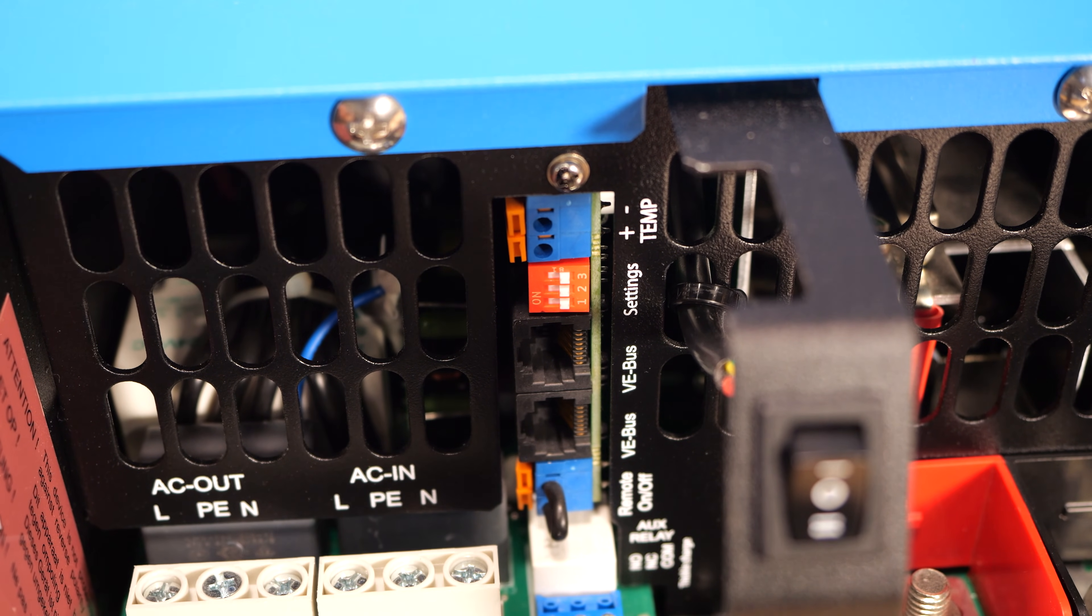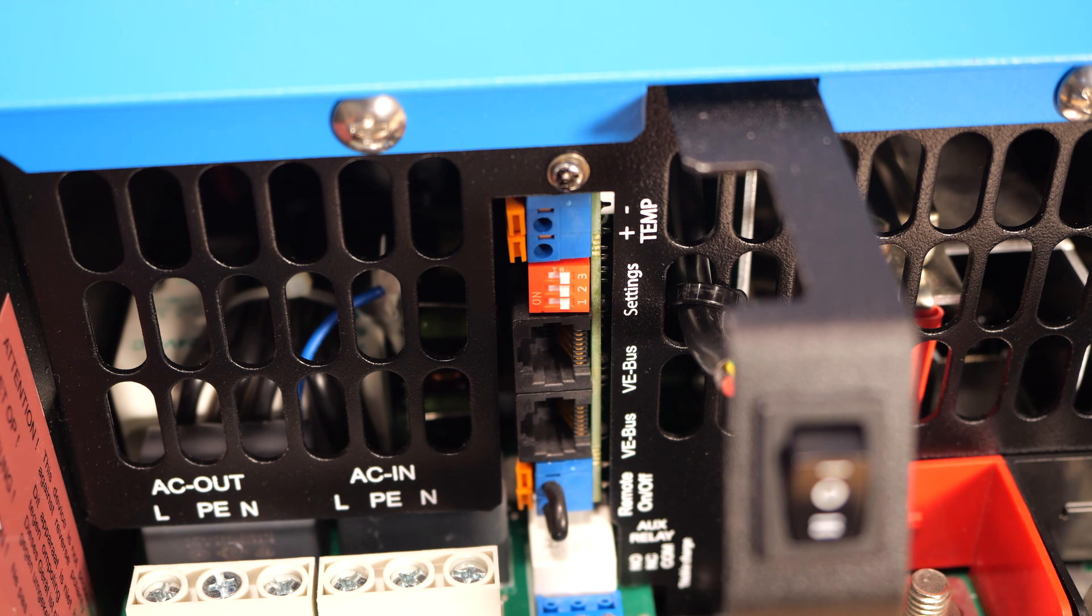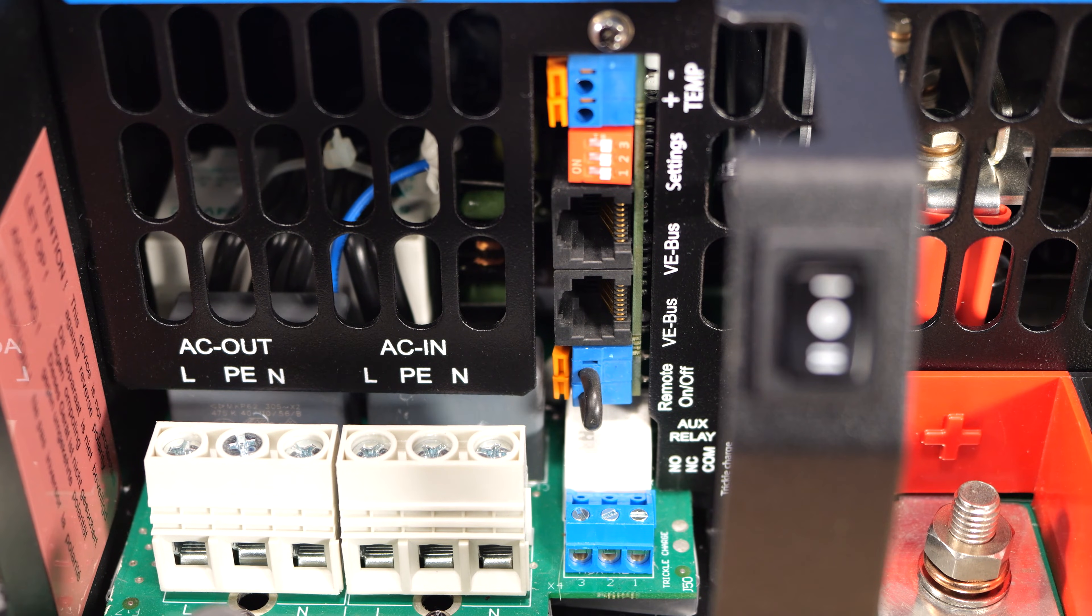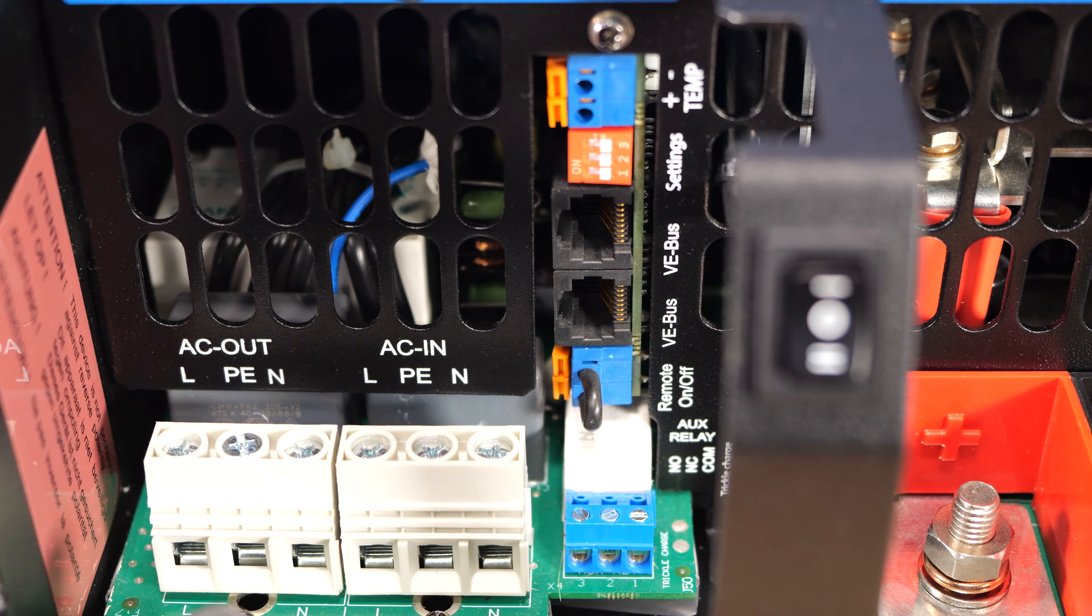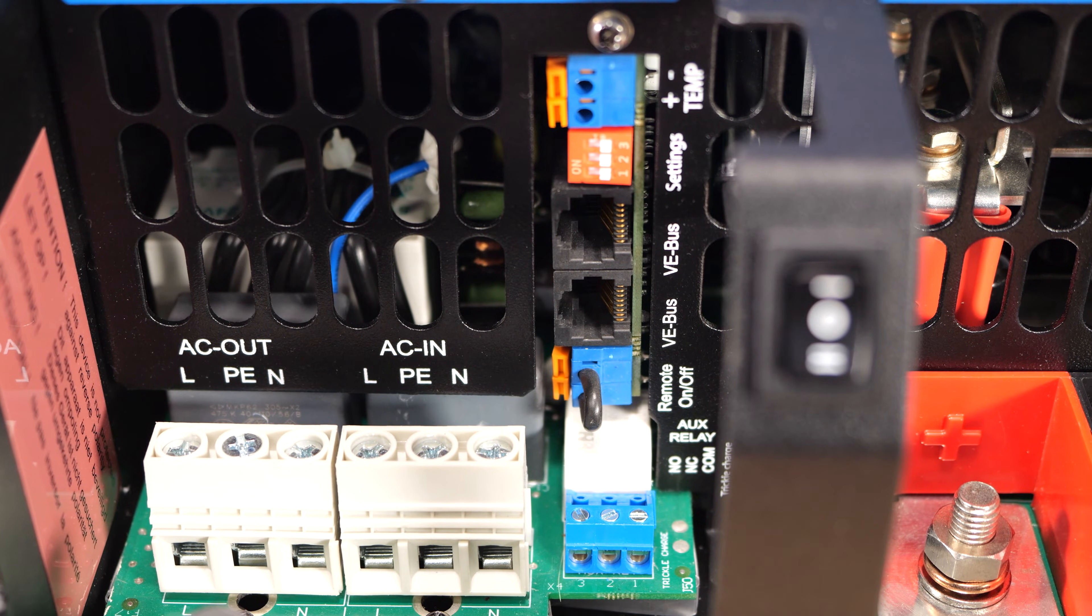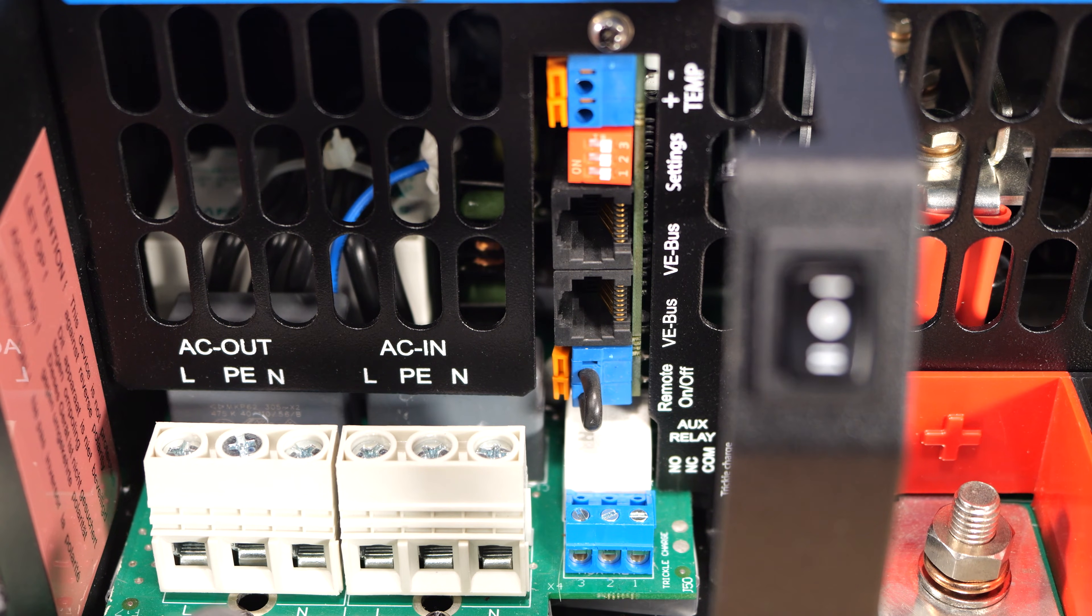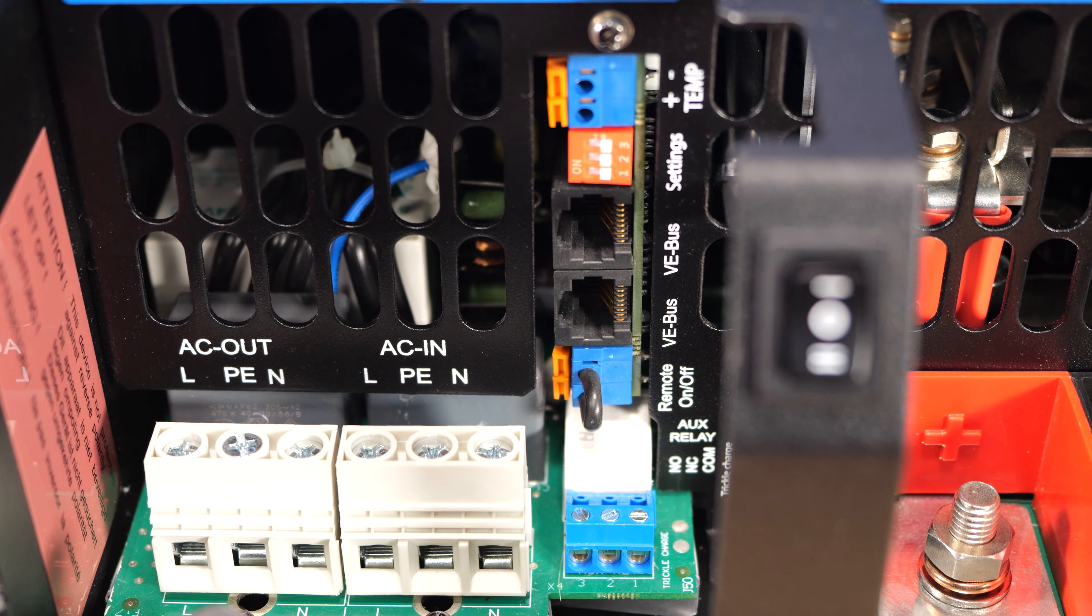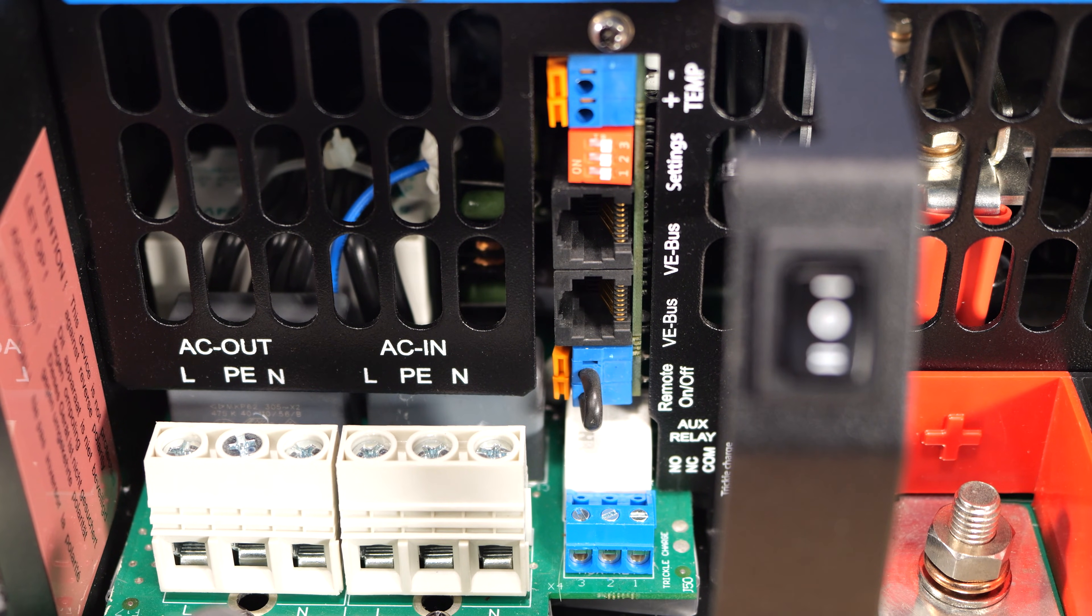And then last but not least, at the top we have a temperature sensor input if you were using lead-acid batteries and wanted to do temperature correction. One thing I will note, though, is that this does not have the external current sensor input. So if you're doing an ESS system, this is not necessarily the best inverter for you. This inverter is best used for UPS or small systems that aren't doing grid backfeed and that type of thing.